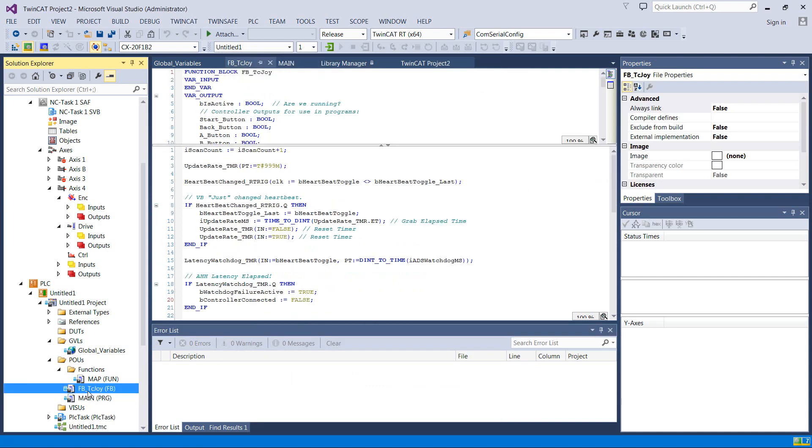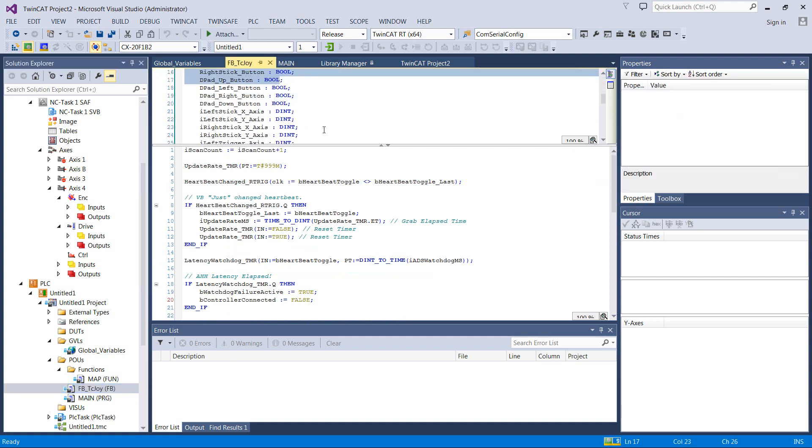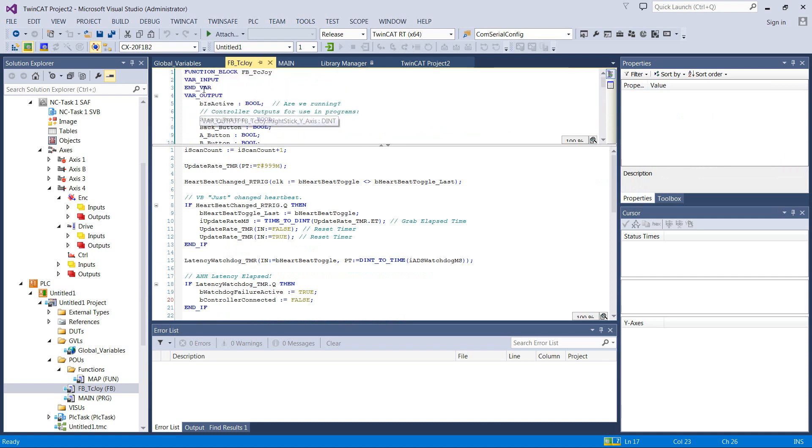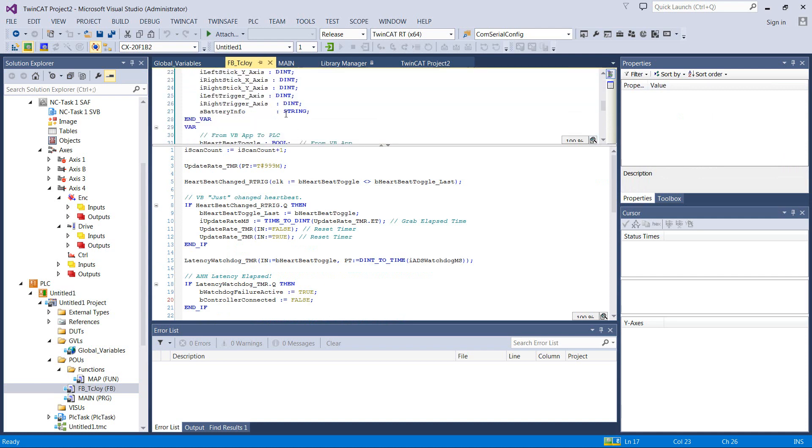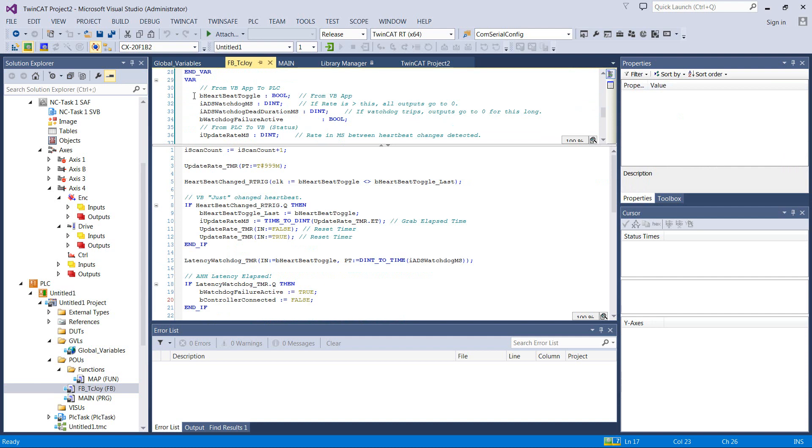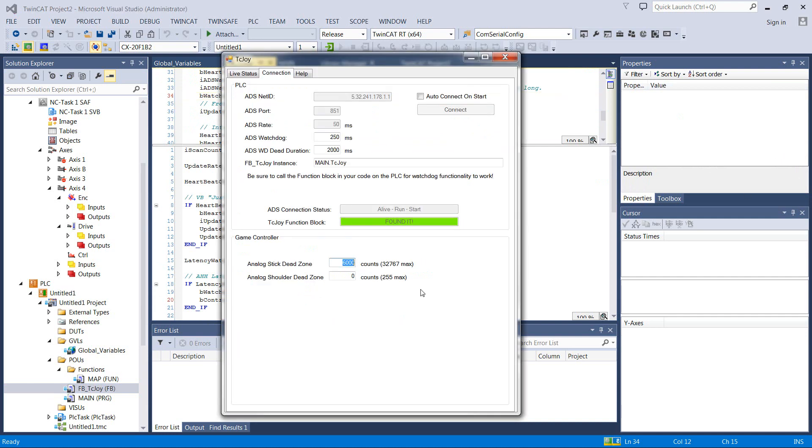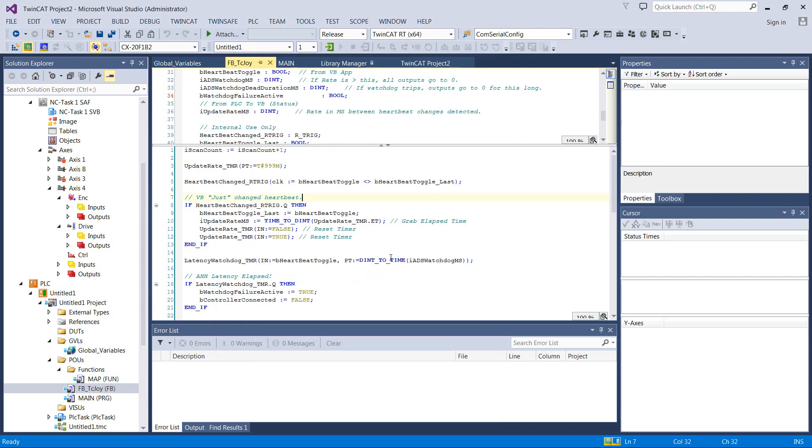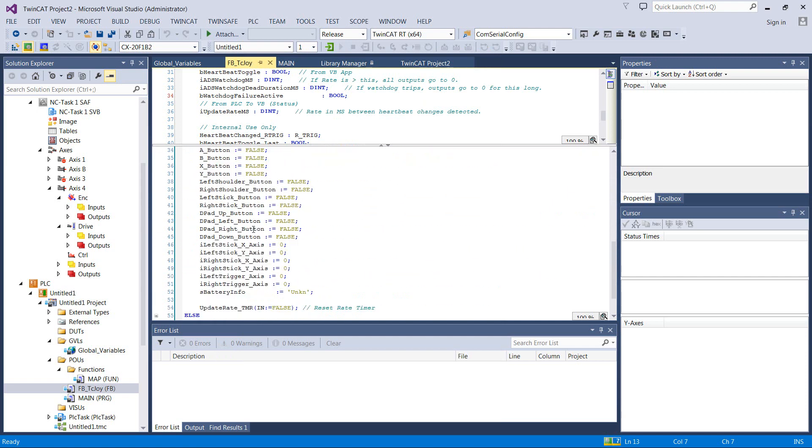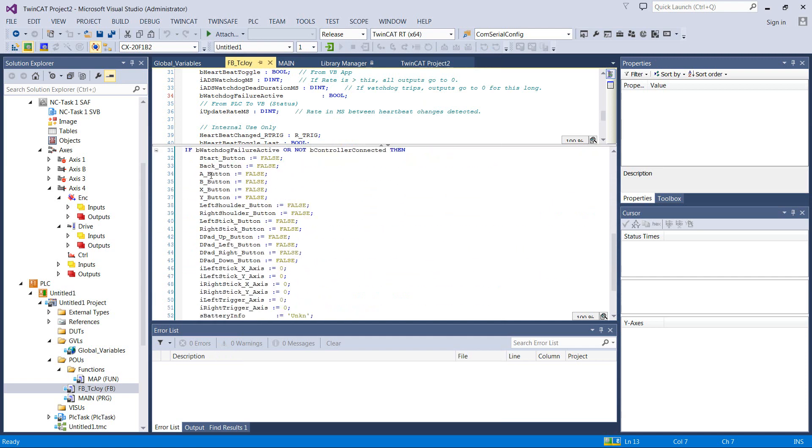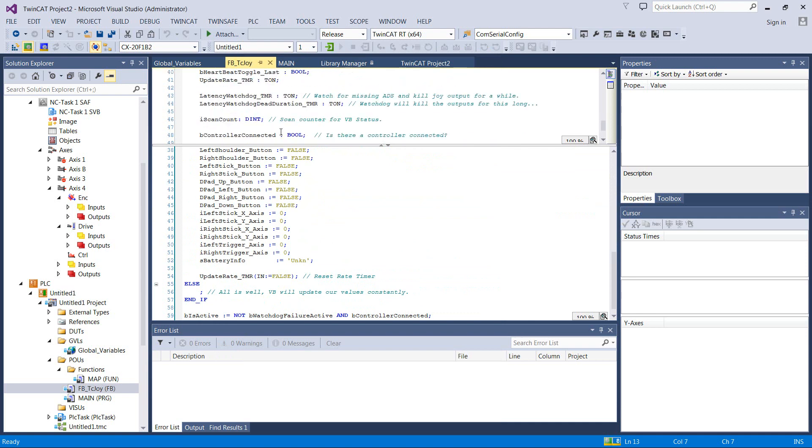So if I come over to the PLC here, I've added in a function block that I wrote. And it's got some inputs and outputs. All these different buttons are inputs, or rather outputs of this function block. And then we've got some locals, and so what I do is watchdog it to where if I don't get a response within the dead time, which is right, the watchdog's at 250 milliseconds, so a quarter second. If I don't get that, then I null all these outputs. So that stuff happens right here. And that's a gist of it.